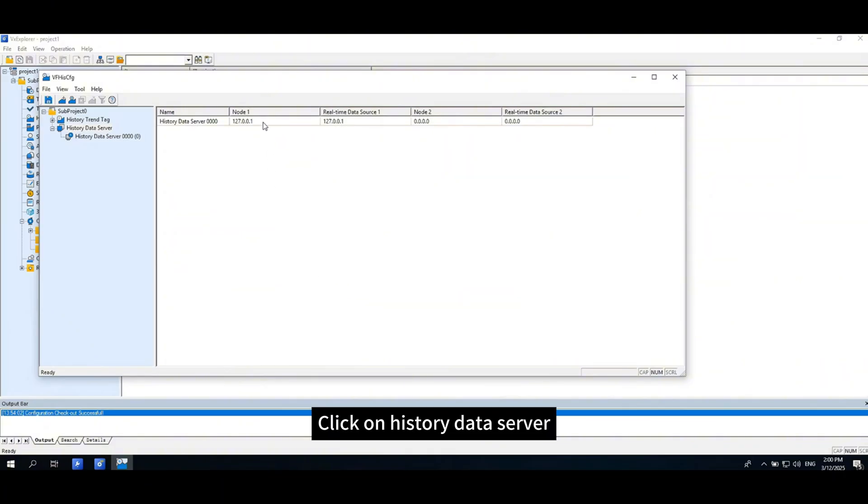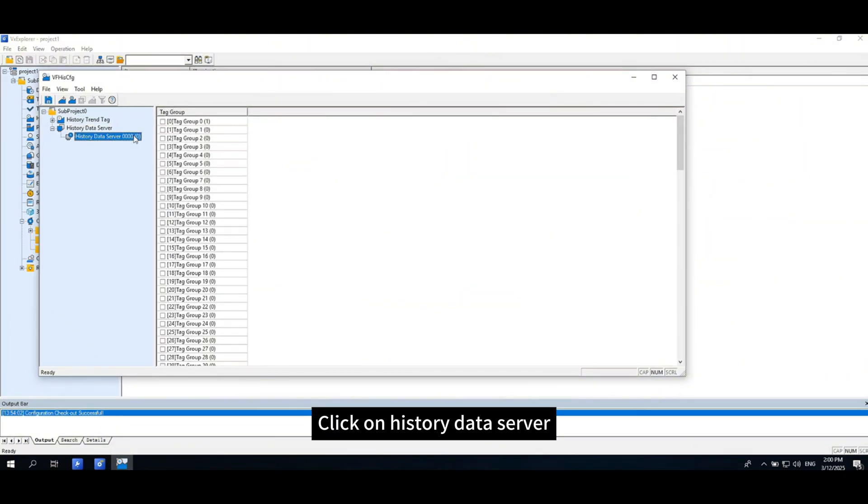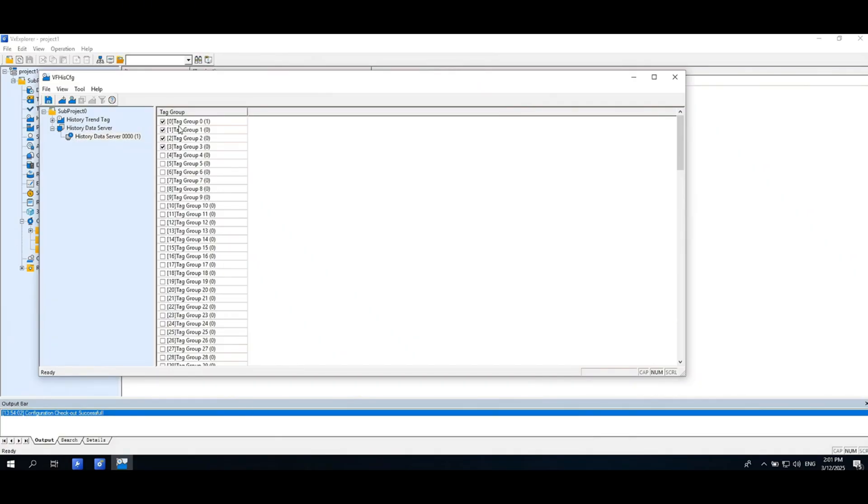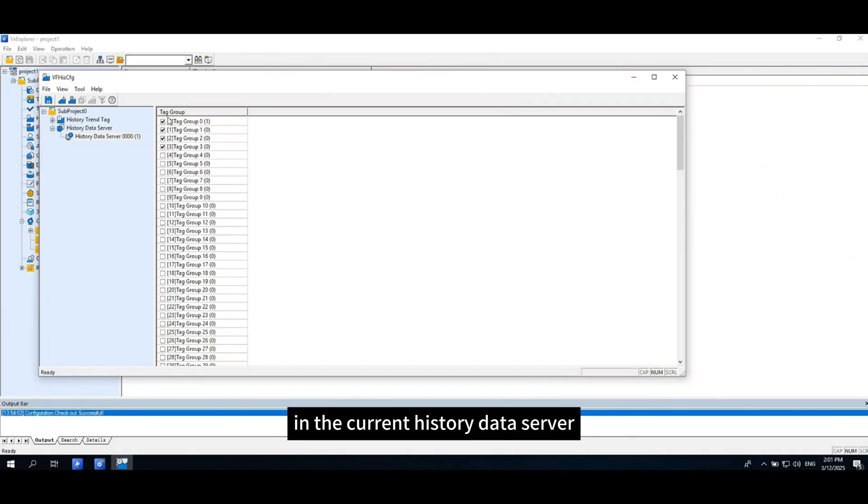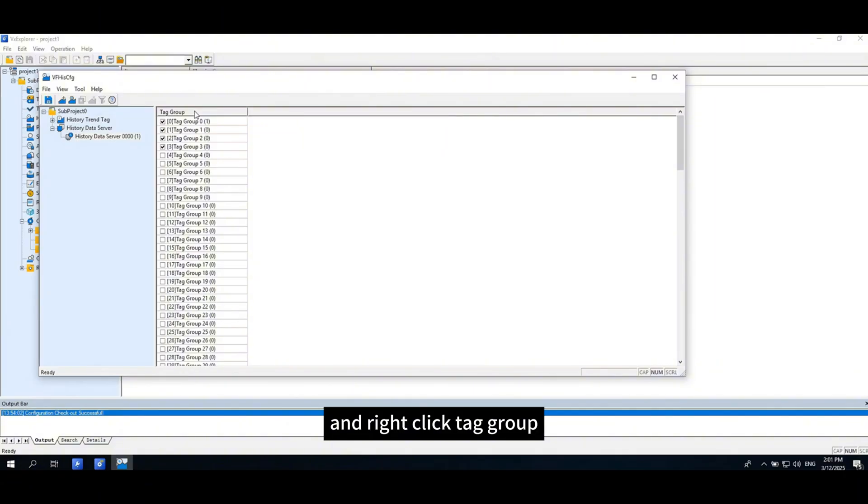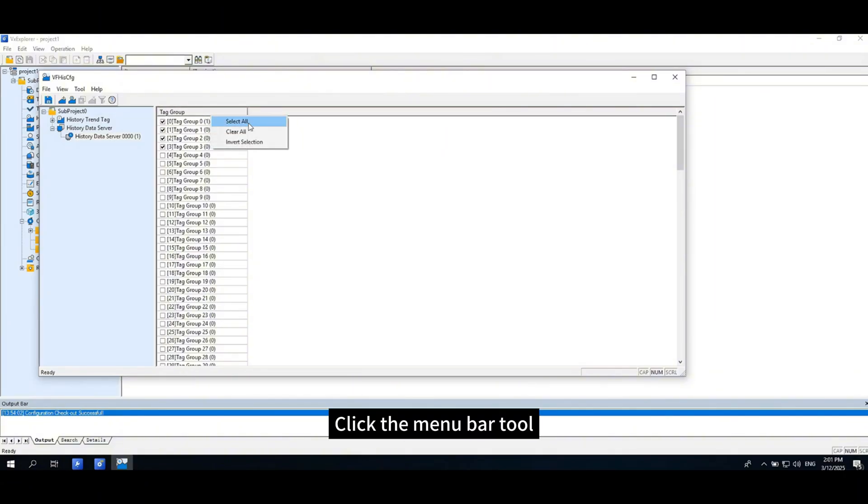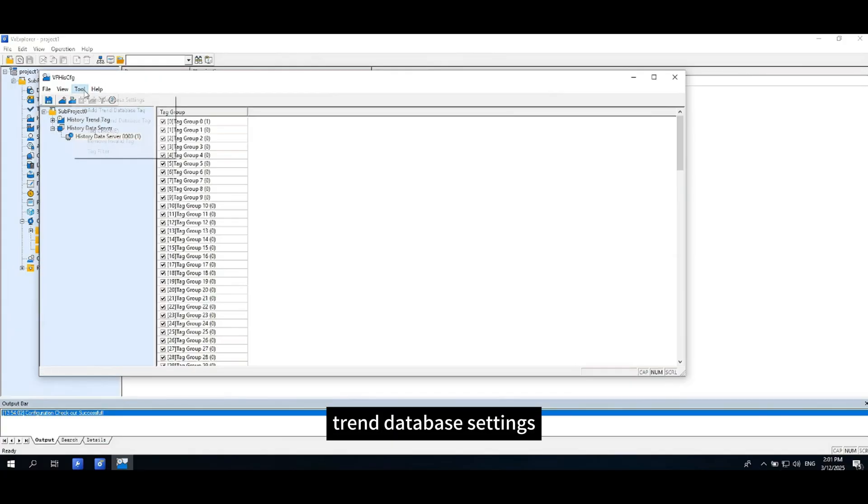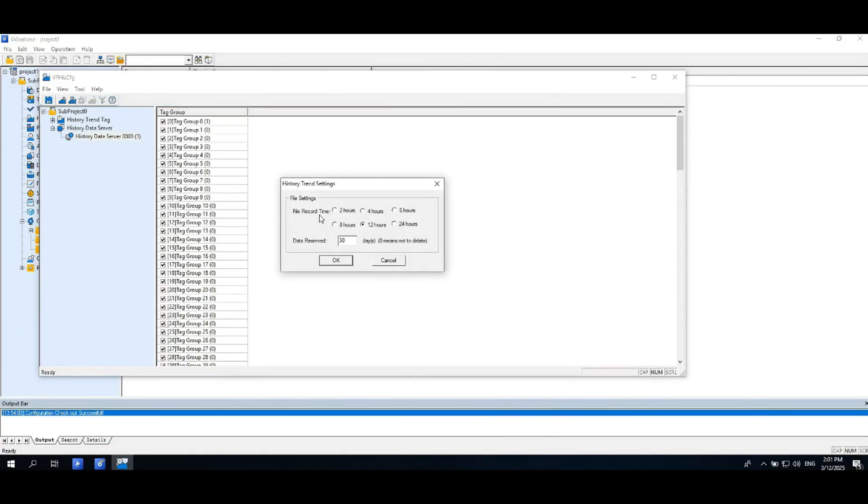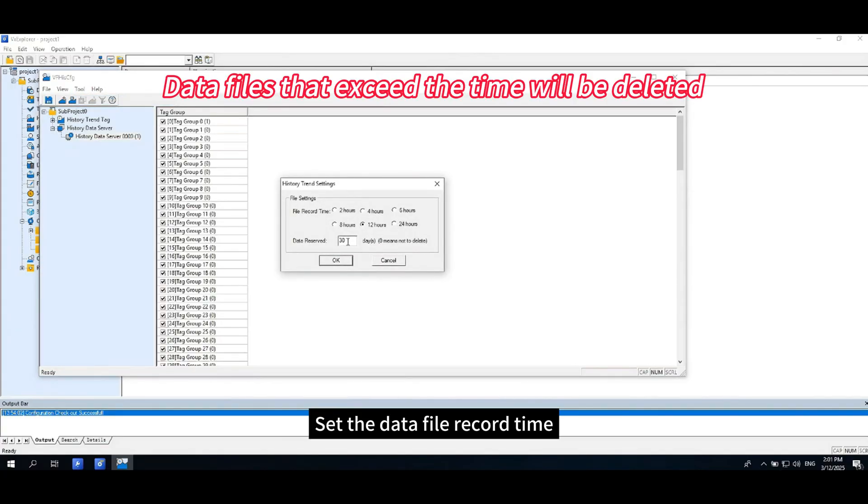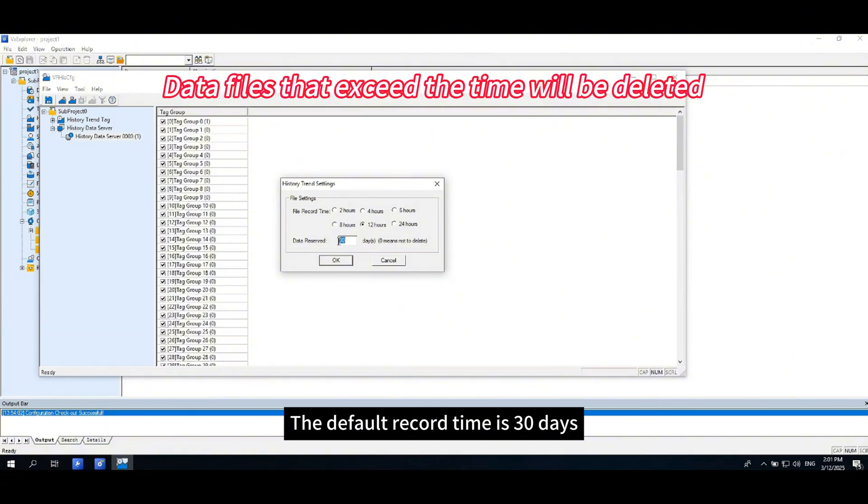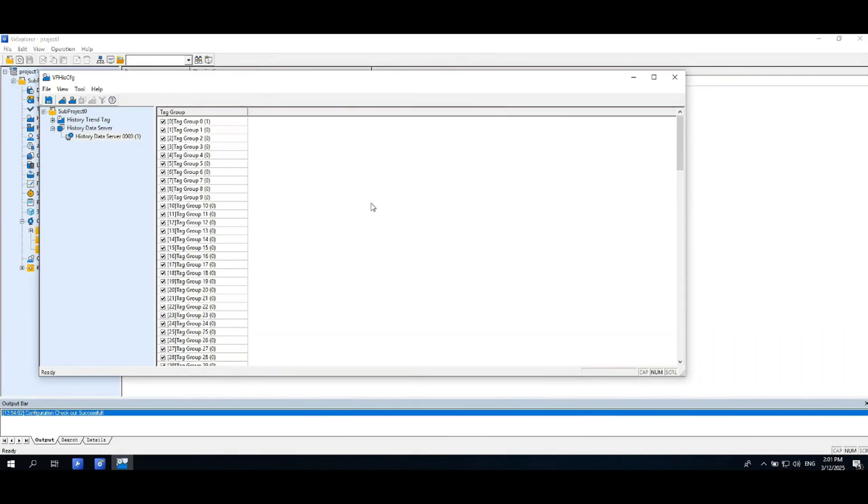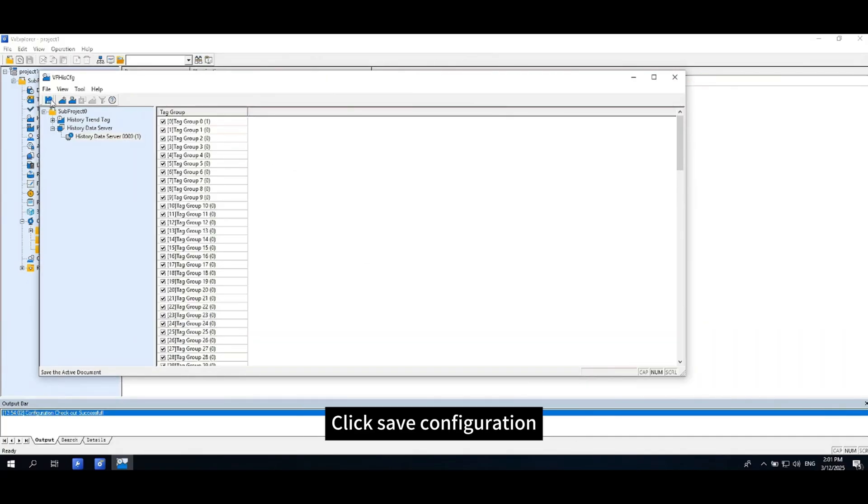Click on history data server. Check the tag group that needs to be stored in the current history data server and right-click tag group. You can select all. Click the menu bar tool, Trend database settings. Set the data file record time. The default record time is 30 days. Zero means no data will be deleted. Click save configuration.